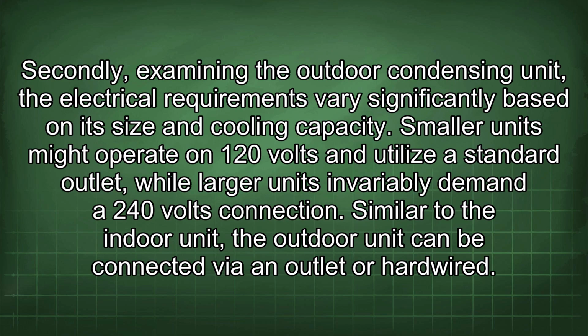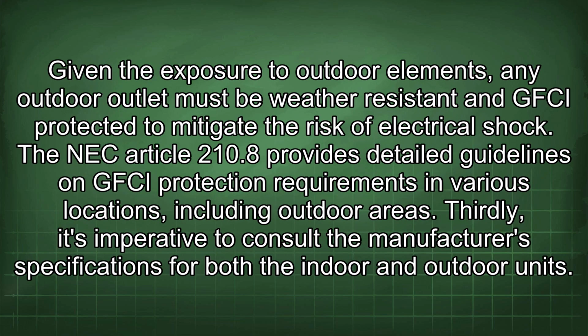The electrical requirements vary significantly based on its size and cooling capacity. Smaller units might operate on 120 volts and utilize a standard outlet, while larger units invariably demand a 240 volt connection. Similar to the indoor unit, the outdoor unit can be connected via an outlet or hardwired. Given the exposure to outdoor elements, any outdoor outlet must be weather resistant and GFCI protected to mitigate the risk of electrical shock. The NEC Article 210.8 provides detailed guidelines on GFCI protection requirements in various locations, including outdoor areas.